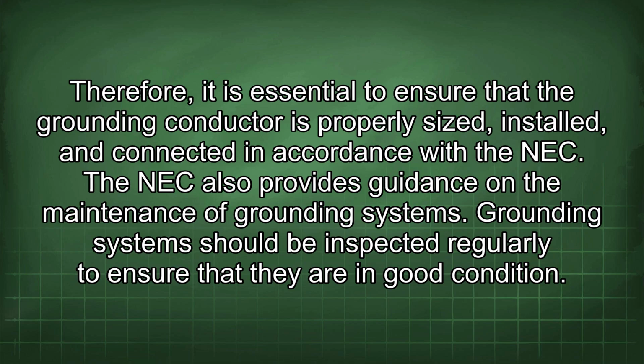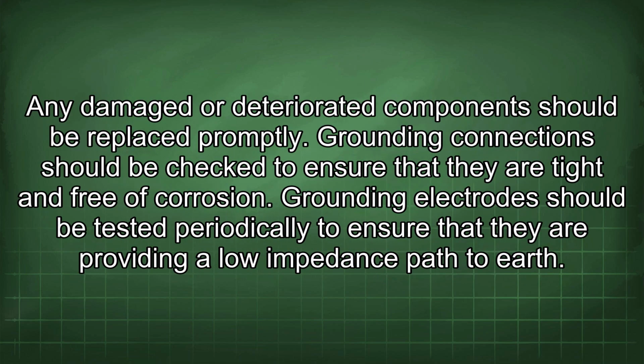with the NEC. The NEC also provides guidance on the maintenance of grounding systems. Grounding systems should be inspected regularly to ensure that they are in good condition. Any damaged or deteriorated component should be replaced promptly. Grounding connections should be checked to ensure that they are tight and free of corrosion. Grounding electrodes should be tested periodically to ensure that they are providing a low impedance path to earth.